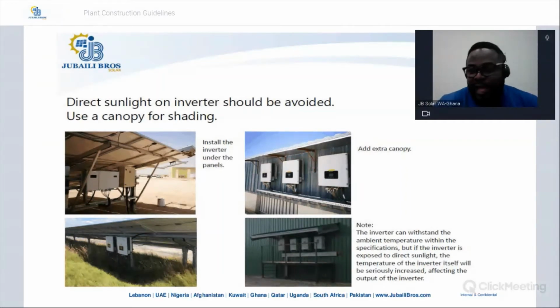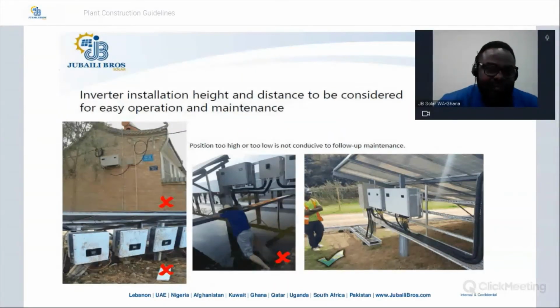Again, as I mentioned earlier, just avoid direct sunlight. I mean, yes, it is IP66. Yes, it's IP67. But let us elongate the lifespan of the inverters by putting a shade. It's always better. Another key point, always make sure that you are installing these inverters at eye level. Remember, there's an indicator panel in front of the inverter, right? That will tell you how the system is working: DC, AC, communication, alarm. Eye level is the best.